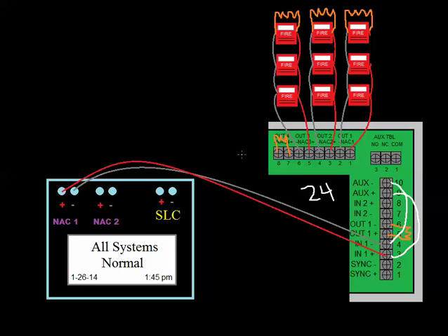So they all have to flash. I think the code tells you, I think it's like twice per second or not more than, whatever it is. And so there are these pulses that are programmed into some of these devices. And there's three main sync codes. And they go by manufacturer. So there's Wheelock, System Sensor, and Gentex.